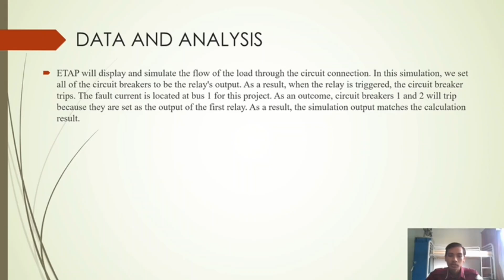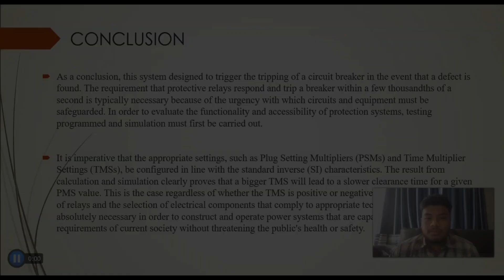Thank you. So next for the conclusion. As a conclusion, the system's purpose is to trip a circuit breaker in incidents where a defect is found, and because of the priority of which circuit and equipment must be protected, a protective relay must respond and trip a breaker within a few thousandths of a second. And to analyze the functionality and stability of the protection system, program testing and simulation must be performed. And the PSM and TMS values must meet the standard of SI properties.